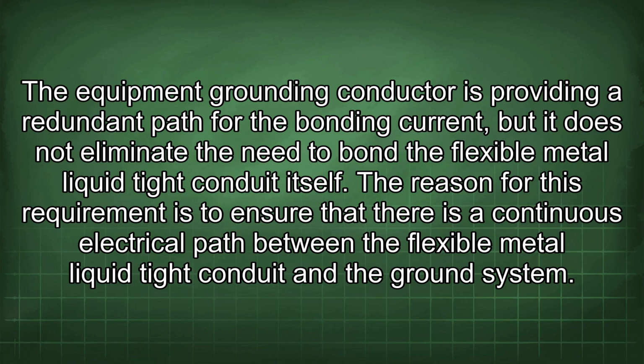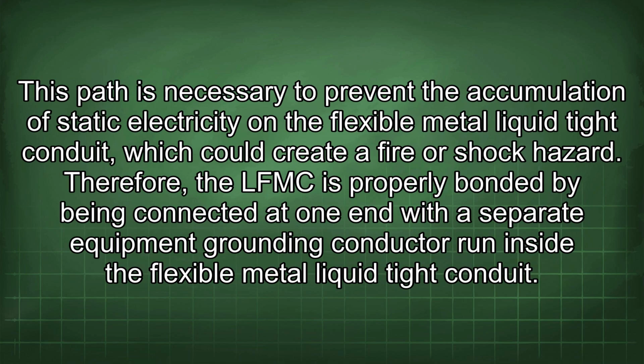The reason for this requirement is to ensure that there is a continuous electrical path between the flexible metal liquid tight conduit and the ground system. This path is necessary to prevent the accumulation of static electricity on the flexible metal liquid tight conduit, which could create a fire or shock hazard. Therefore, the LFMC is properly bonded by being connected at one end with a separate equipment grounding conductor run inside the flexible metal liquid tight conduit.